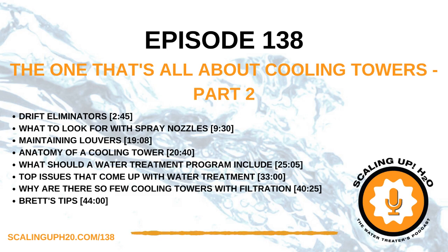I'd love to, and I'd like to talk a little bit about why I'm excited about the drift eliminators and the very little drift that happens today. Quite frankly, it's because of Legionellosis prevention. I want to clarify the term I used, Legionellosis, not Legionella. Legionella is the bacteria, so we still need to treat that, there needs to be a plan, all of that needs to be in order. The drift eliminators do a great job minimizing the risk for that Legionella to come out of the cooling tower so somebody can inhale it and get Legionellosis. Can we talk a little bit about that?